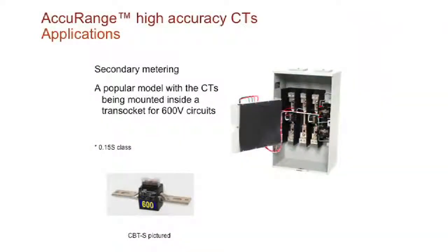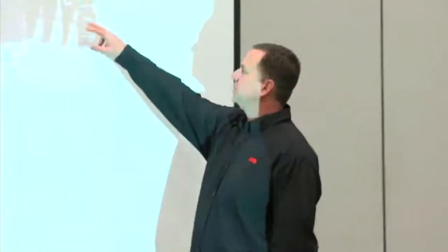This particular unit, called the CBTS, these are very commonly found in what we call a trans socket. This is what you'll find on the side of a gym or a McDonald's or a CVS type of application or type of installation. And then you would typically have a meter box right next to it where the data would be fed into the meter. You can see these are bar type. You can actually kind of see right here the bars on either side of the current transformer inside the trans socket. The primary would be loaded into that and coming back out and then flowing into the store or whatever other installation there is.